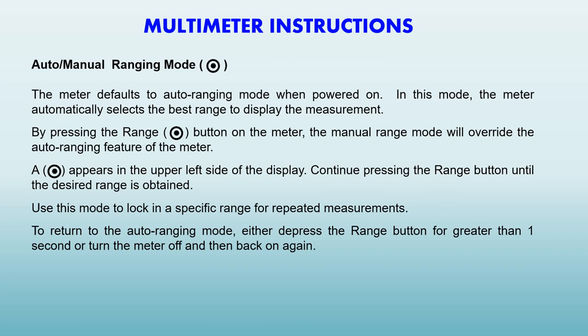To understand a little about these meters, first we have the auto manual ranging mode. This meter defaults to auto ranging mode when powered on. In this mode, the meter automatically selects the best range to display the measurement. By pressing the range button on the meter, the manual range mode will override the auto ranging feature of the meter. A bullseye appears in the upper left side of the display. Continue pressing the range button until the desired range is obtained. Use this mode to lock in a specific range for repeated measurements. To return to the auto ranging mode, either press the range button for greater than 1 second or turn the meter off and then back on again.